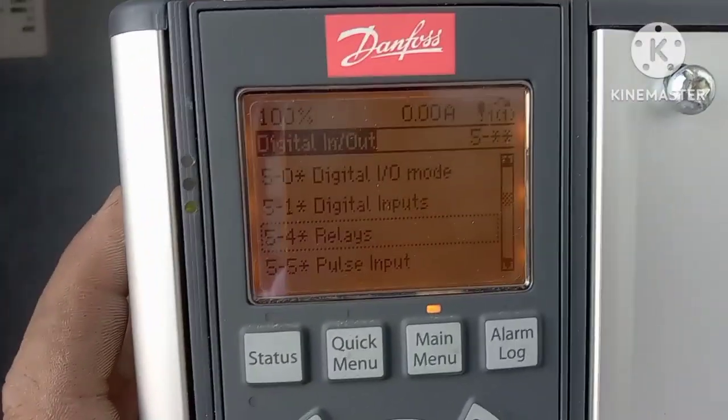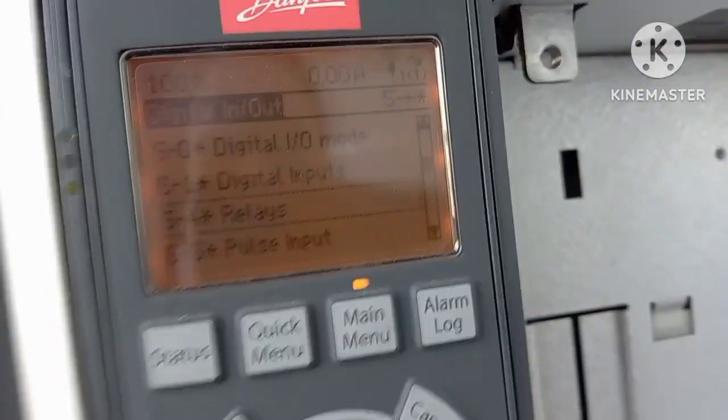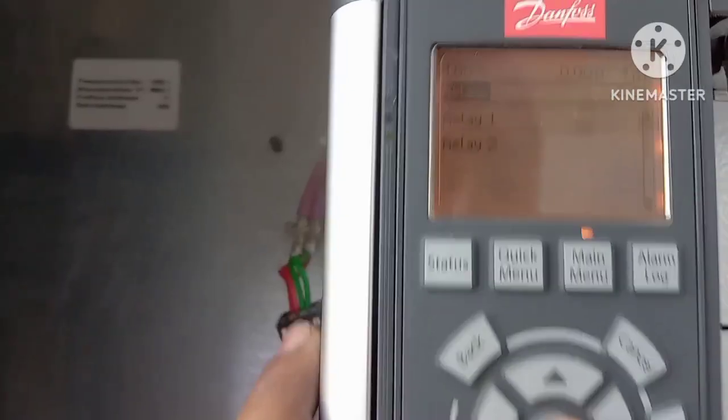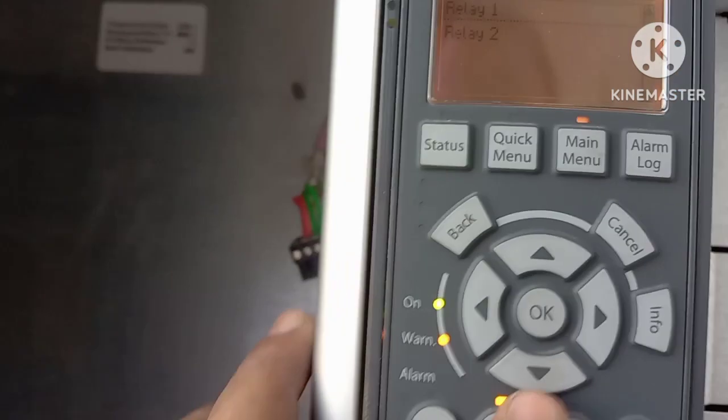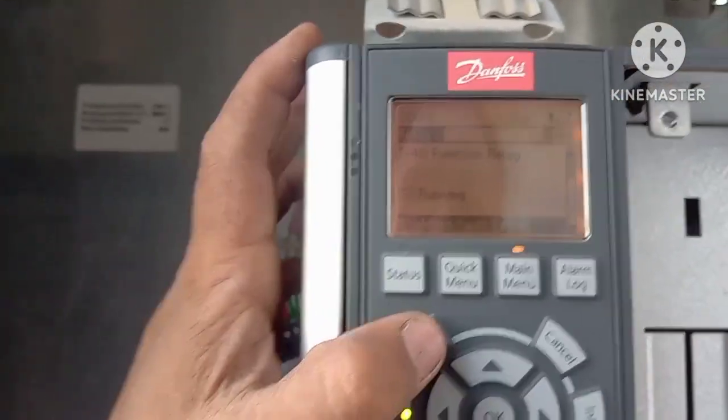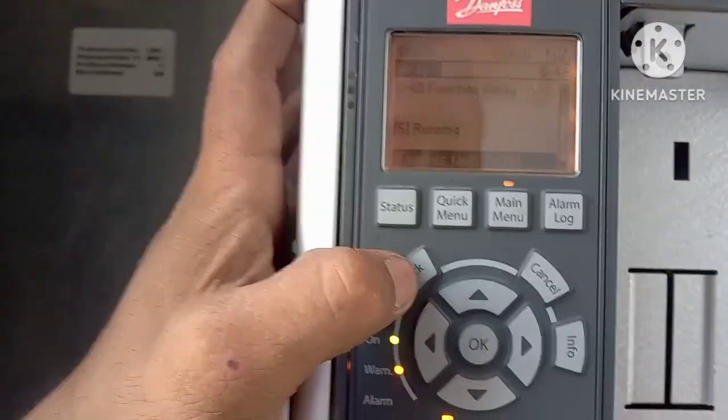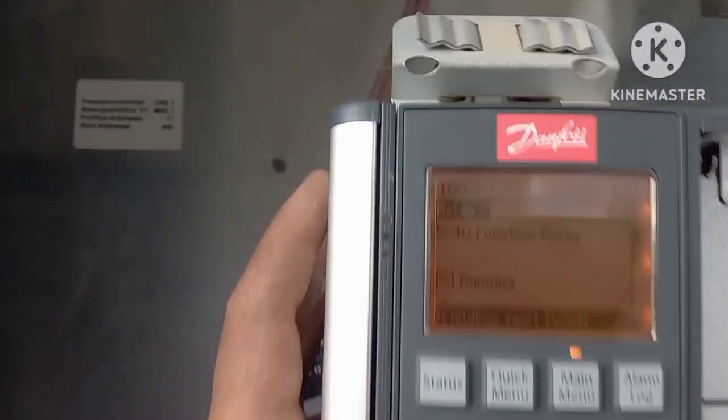If you want to use relay output, there are two relays available for alarm or indication control — alarm lamp control or as per your requirement. Relay 1 is set to alarm, and Relay 2 is set to running. So one relay will activate when any alarm occurs, and the other will activate when the VFD is in running condition.